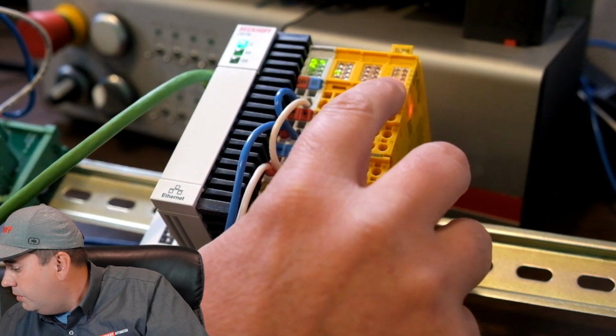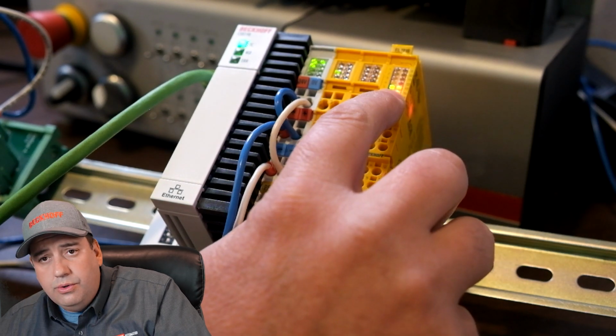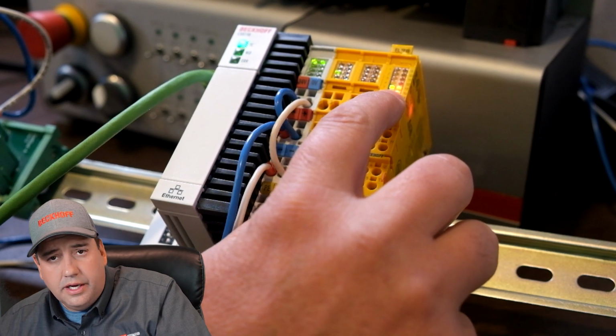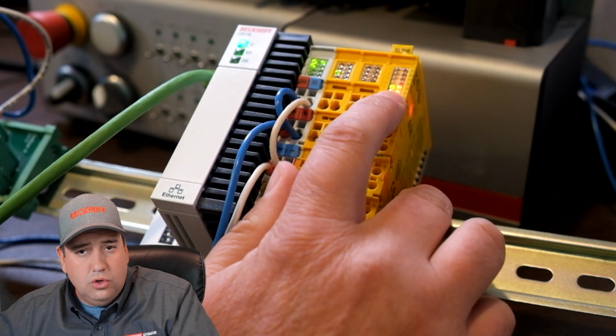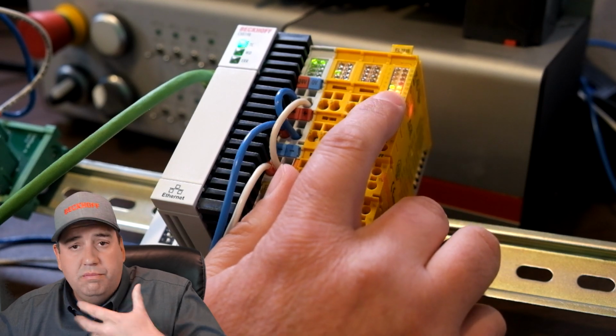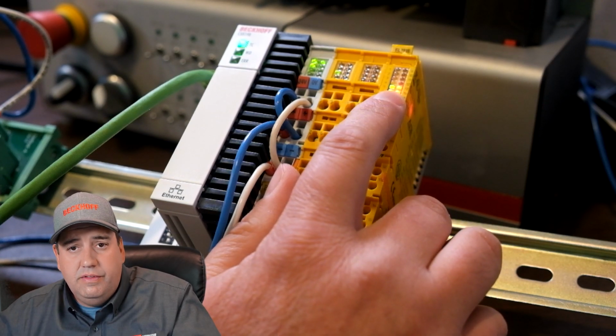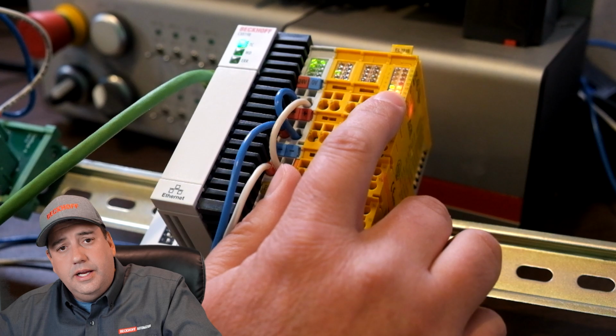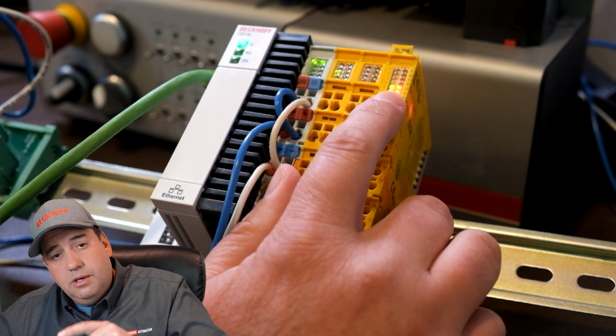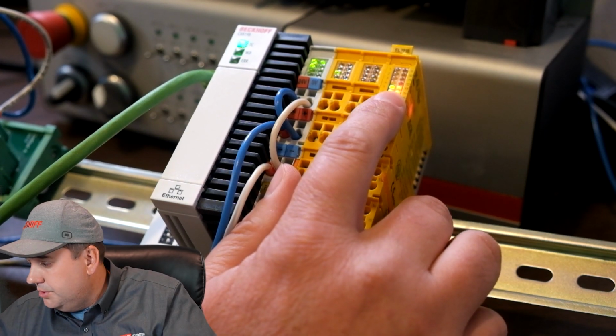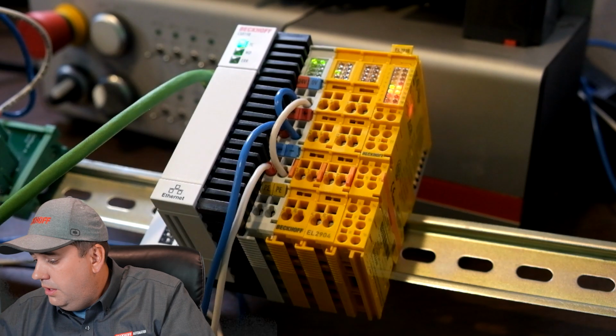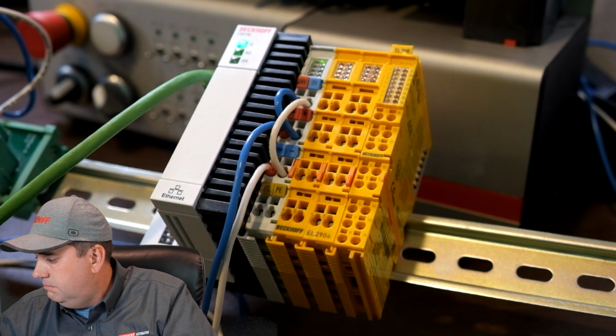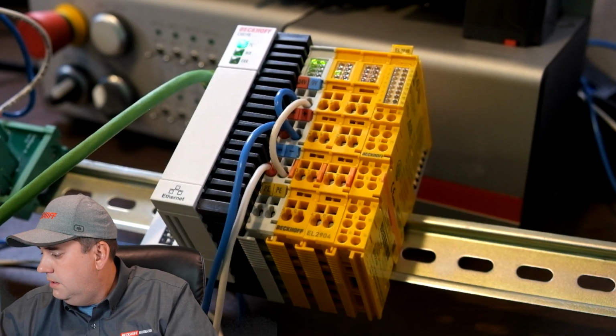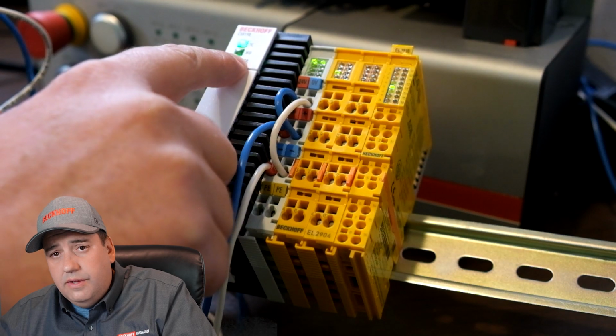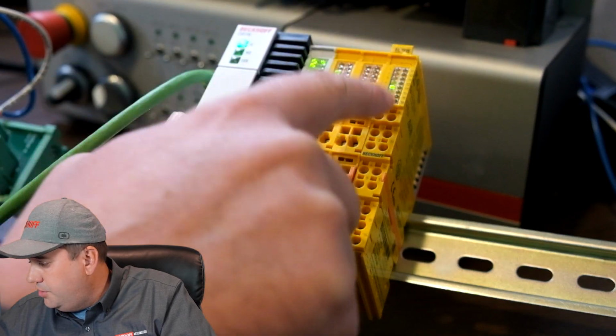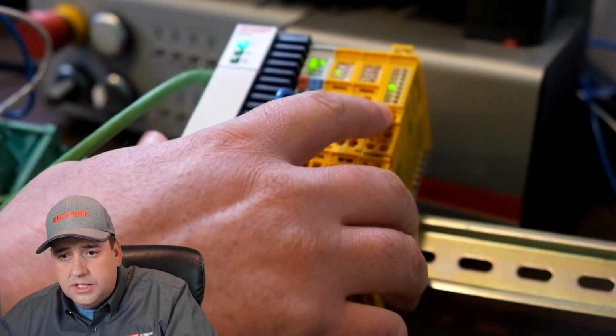Now if we look at the terminal, we can see that we have diag lights 2, 3, and 4 all turned on. This means a global shutdown has occurred. Basically, we pushed a mismatched version of the software into the terminal, but because we're backward compatible, this error is resettable. So again, all we're going to do now is power cycle. You can see I didn't even give the CX time to shut down fully. I'm just really resetting the terminal itself.